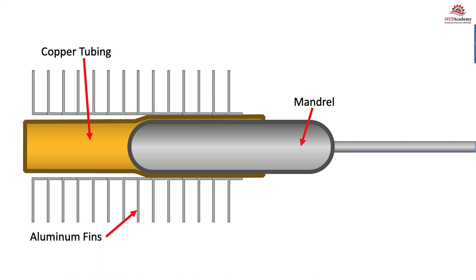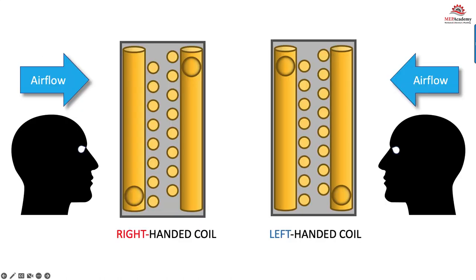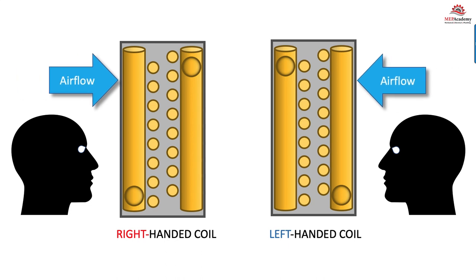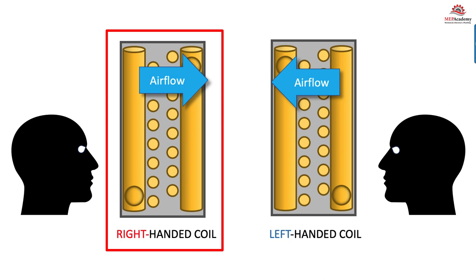The fins surrounding the coils can be configured in various shapes, from flat to corrugated. Coils are considered left-handed or right-handed. This is important because when the coil is installed, you want to make sure that the piping connections are on the correct side of the equipment to avoid extra piping. This can be determined by standing in front of the coil, looking in the direction of airflow with the air at your back. If the connection is on your right, it's a right-handed coil connection; if it's on the left, then it's left-handed.